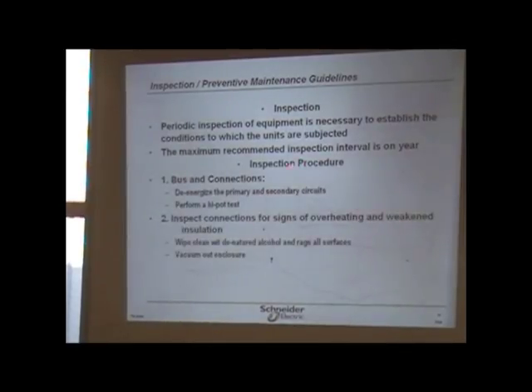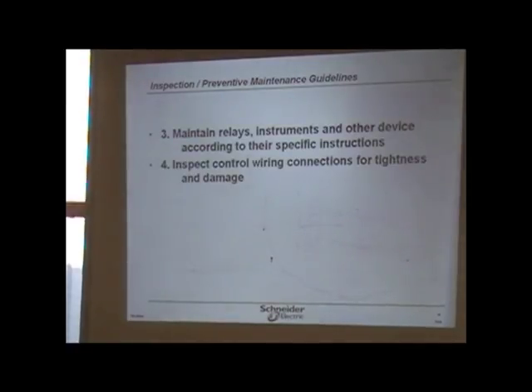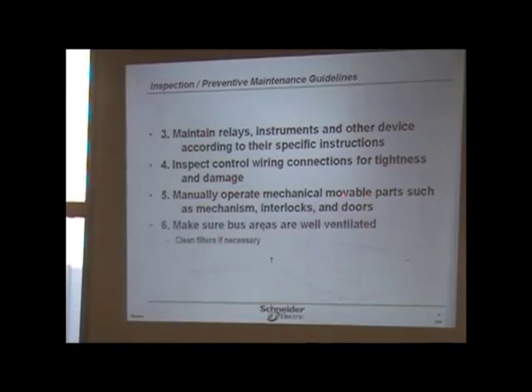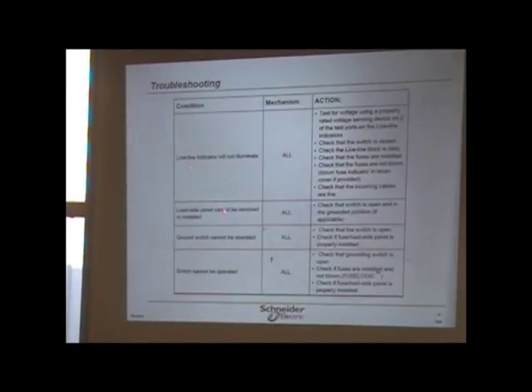Again, recommended inspection interval 1 year. Once again, you're looking at your bus connections and stuff like that, or the other, perform a high pot test against signs of overheating. This is almost repetition of what we just, like I said, the process is the same. You're going to operate everything. You make sure that the bus areas are well ventilated, the filters are clean, and then you come back down to your troubleshooting.